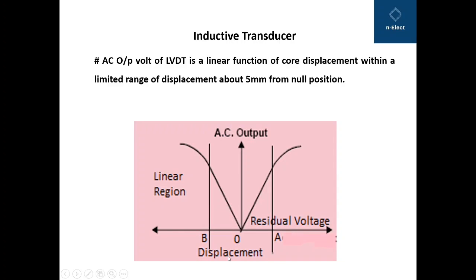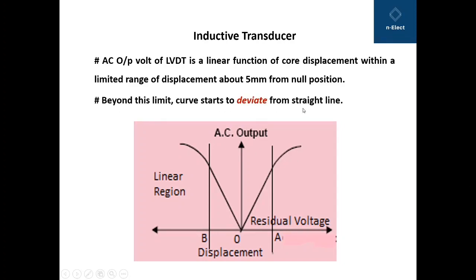The AC output voltage of LVDT, shown on the y-axis, is a linear function of core displacement, shown on the x-axis, within a limited range of about 5 mm from the null position — 5 mm to the right (point A) and 5 mm to the left (point B). The curve is very linear within this ±5 mm range, but beyond 5 mm it deviates from linearity.